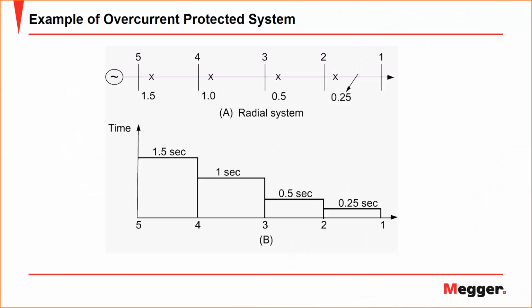If, for example, I have a system like this where I have multiple bus bars and each bus bar having a radial system, lines connecting each other. When a fault happens at the end of the line between bus bar 1 and bus bar 2, the trip time becomes the shortest. And this is to achieve selectivity, because this fault will be seen by all the relays in bus bar 2, 3, 4, and 5. So I want only relay 2 to trip, which is the faulty part. I set the time at relay 2 to be the lowest, and it becomes higher in the upstream bus bars.